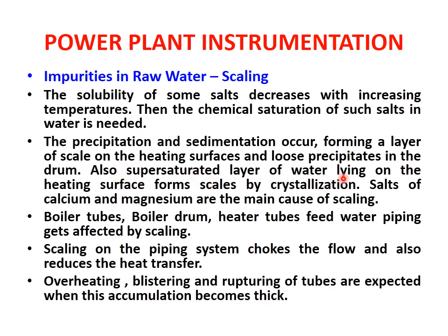Then the next point is, a supersaturated layer of water lying on the heating surface forms scales by crystallization. So due to the crystallization of the salts, because the supersaturated layer of water will be present inside the boiler, the scale formation will take place. Salts of calcium and magnesium are the main cause of scaling. As we have mentioned earlier, the dissolved salts cause more scaling.